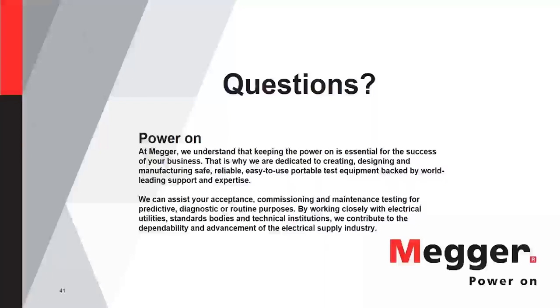Okay, thank you, Volney. Next question. Our battery chargers have ground detectors. If there are no ground alarms on the charger, is that enough to satisfy the verify for an unintentional ground requirement, or does this have to be verified by a meter? The actual standard doesn't define exactly how you have to do this, so you have the liberty of defining how you're going to do it. If you have a ground detector, that can be fine. But you have to document that you've checked it and that there's no indication of a ground fault. If you don't have one, you just take a meter and measure from each side to earth and see if they're equal within the requirements.